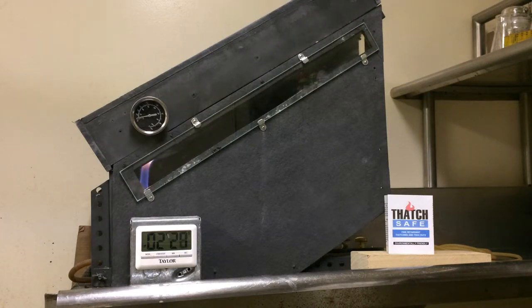This test usually lasts for approximately 4 minutes, and the 4-minute burn under the ASTM D3806 standard correlates to the 10-minute test that is done on the ASTM E84 or the UL 723.